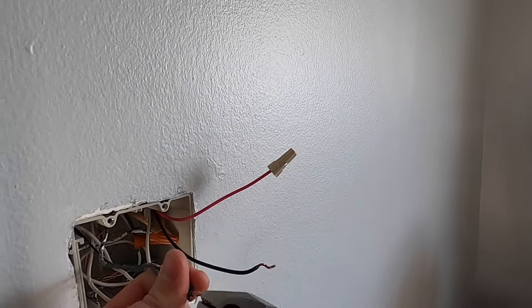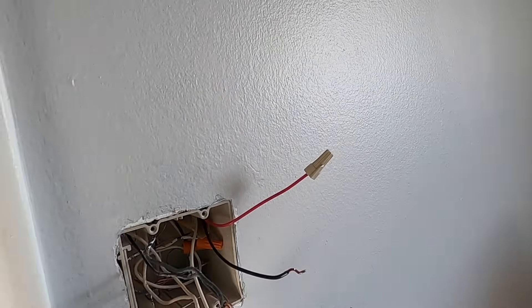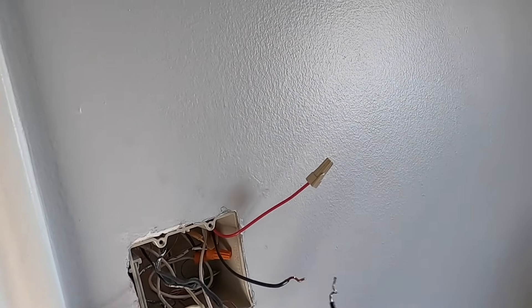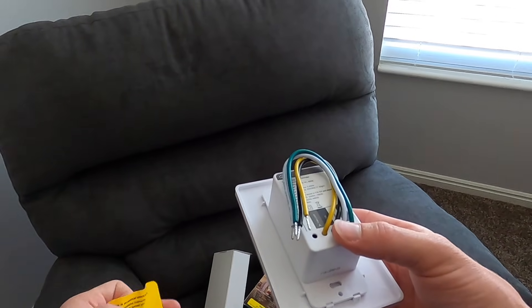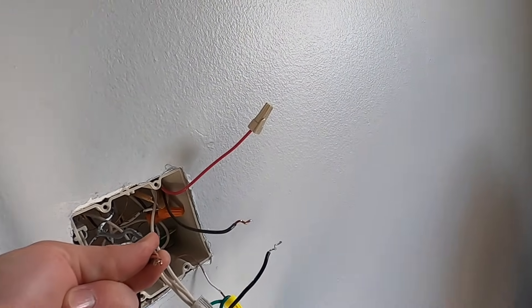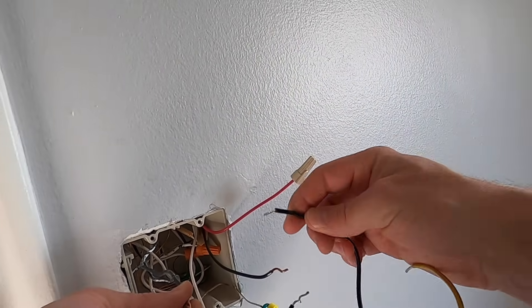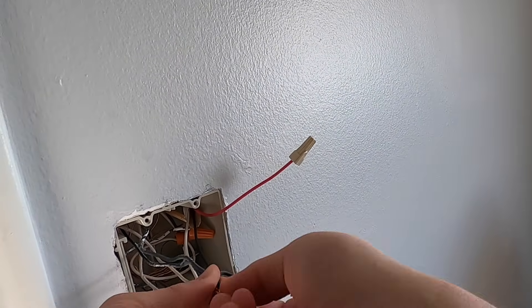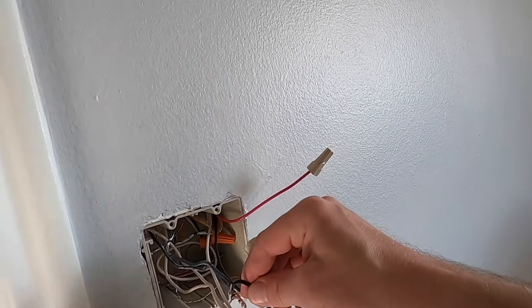Now since the line of power coming from my circuit breaker is coming to my box, I need to connect all these black hot wires to each individual switch so that each circuit has power connected to it. These smart switches come with a pigtail often already attached. So then each black pigtail coming off the switch needs to connect to the power that goes to the circuit breaker. Oftentimes these wires that come from the circuit breaker will also daisy into another. So you may have multiple black wires connecting at the box.